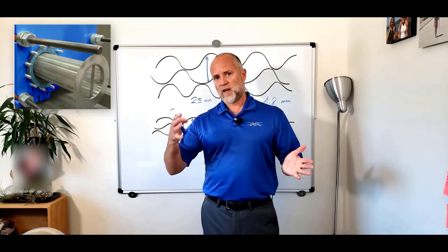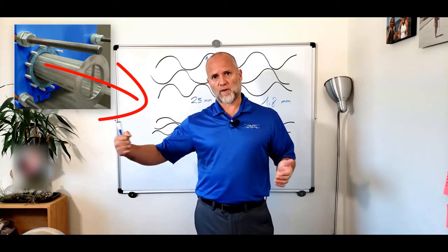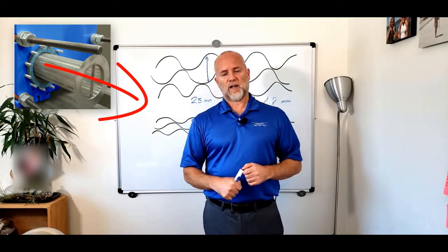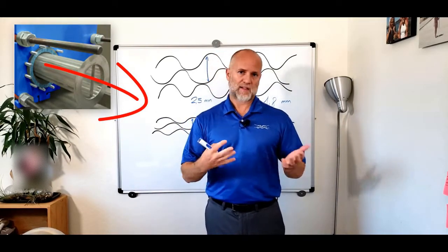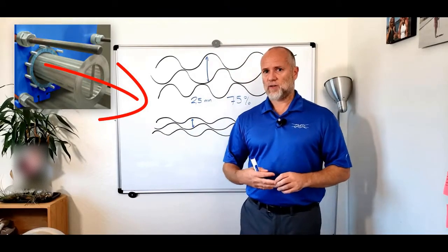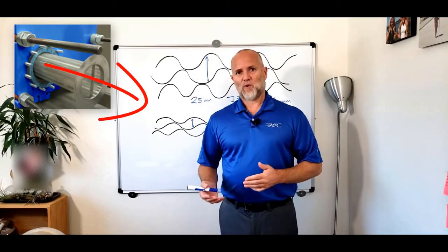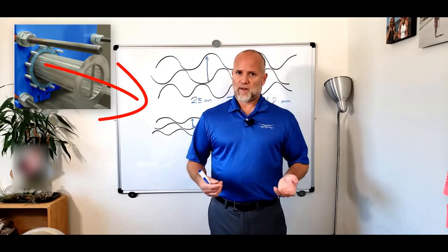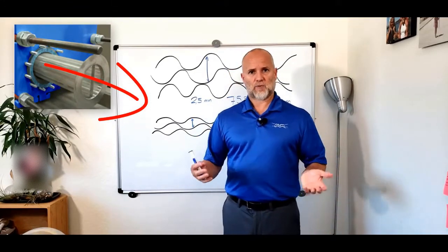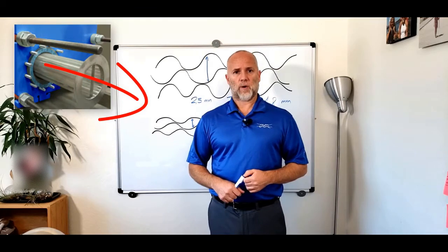As you can see, you pull the port filter out from the inspection port on the back. So as a strainer, you don't have to disconnect the heat exchanger. Of course, you have to stop the flow and close the valves, but other than that it's a minor disruption of your operations.